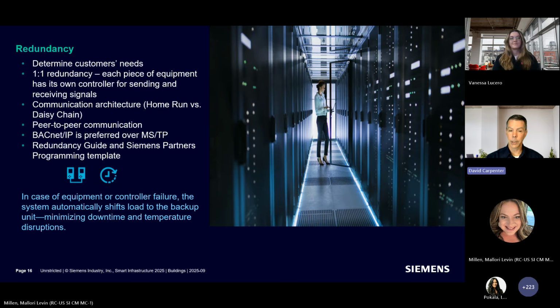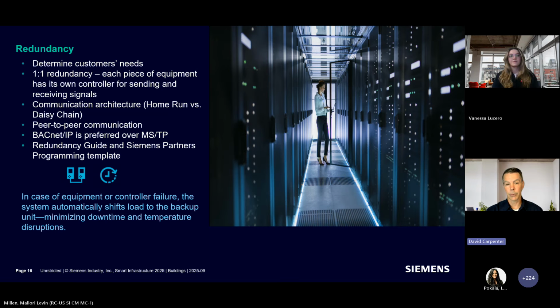The old automation redundancy thought was that we would have multiple controllers controlling one set of I/O, because controller life, reliability was a weak point. And some of the equipment, the physical machinery, was more reliable than the controller. Now that is not the case, and we have good reliability in the controllers, and so redundancy has become one controller for every piece of equipment that's controlling. And each controller has its own set of I/O for its own set of equipment. That way, everything is redundant, the controller and the piece of equipment.